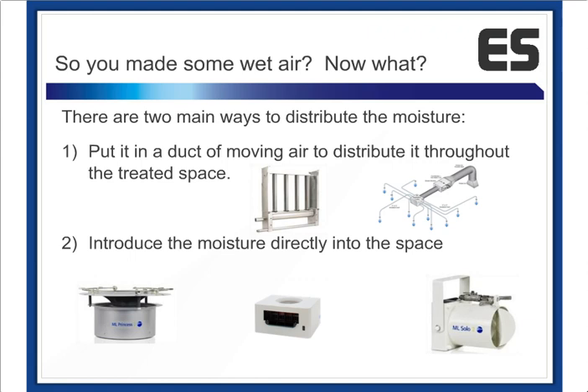That would be a central means of distributing it through your building. Below, you'll see 3 different means of distributing moisture. The one in the middle is a blower for blowing steam directly into a space, like in an MRI room. We use these very frequently, a little humidifier with a little blower to make sure the humidity is right.